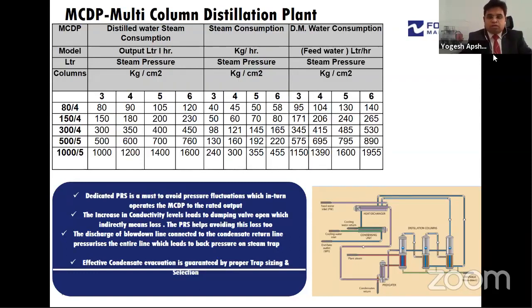If we look at any manufacturer's catalog, they give the range of steam pressure, the range of water pressure, and the water consumption. If we look at this graph or table, with a consistent steam pressure of more than 5 or 6 bar, there is a consistent output from the WFI still, and the DM water consumption is also very good. So it is very important to have a dedicated pressure reduction station for the MED or WFI still, and a dedicated pressure reduction station for the pure steam generator.